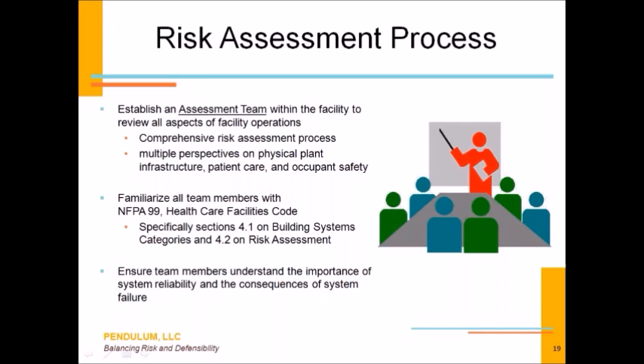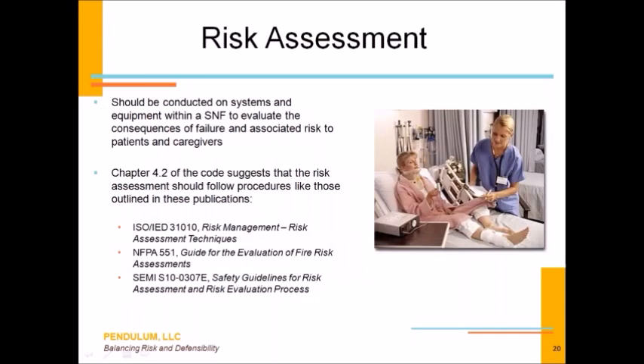When it comes to the risk assessment process, so you can apply NFPA 99, you've got to establish a risk assessment team so that you can assess the risks associated with your healthcare facility's operation and determine which elements of NFPA 99 apply. Now, neither CMS nor NFPA tells you exactly, it doesn't prescribe the risk assessment process or who should be on that risk assessment team. You definitely want a team approach so that you get multiple perspectives when assessing the risk, which we're going to talk about in a second here. But there are some suggested ways of putting that risk assessment team together, and some suggested processes on how to conduct a risk assessment.